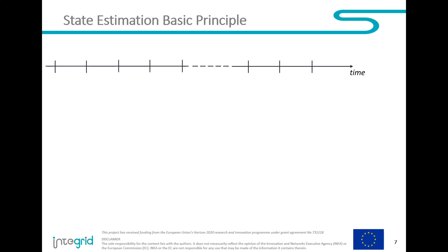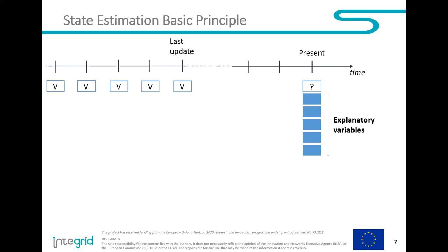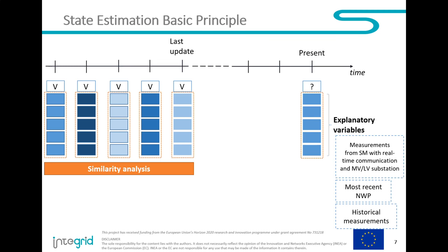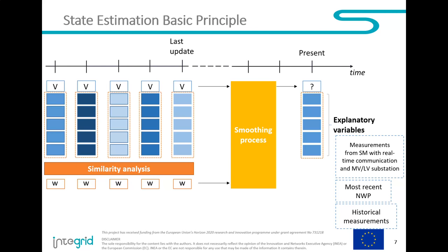The concept is quite simple. We want to make an estimation for the present using the last update from the previous day — metering active power and voltage — to know what is happening on the low voltage grid now. We have voltage from the past, historical data, and construct a set of explanatory variables: measurements from a few real-time meters, weather predictions or measurements, historical data, and substation data. We look into the past for similar situations, give a weight based on similarity, and combine everything to estimate voltage at a specific moment.